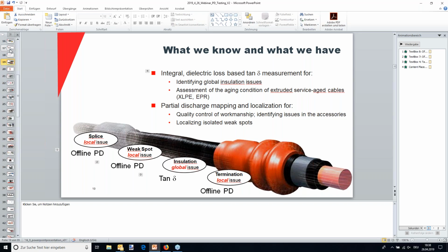And on cables, you do the mapping, you get the activity, you look at the count. That's what I do after I looked at the magnitude. So you look at how many events were triggered, and then you say, okay, where's the weak point, and then you just compare it to the next measurement.